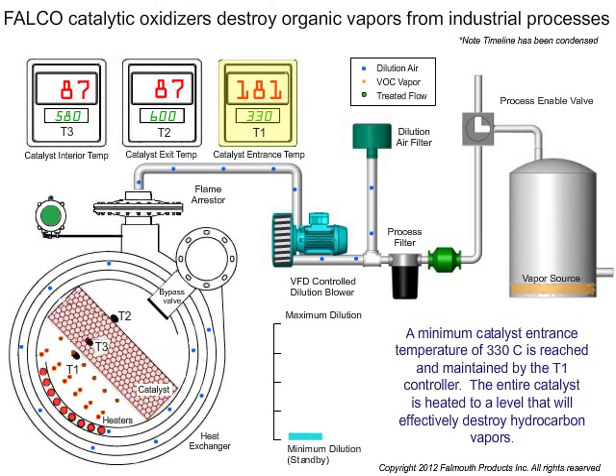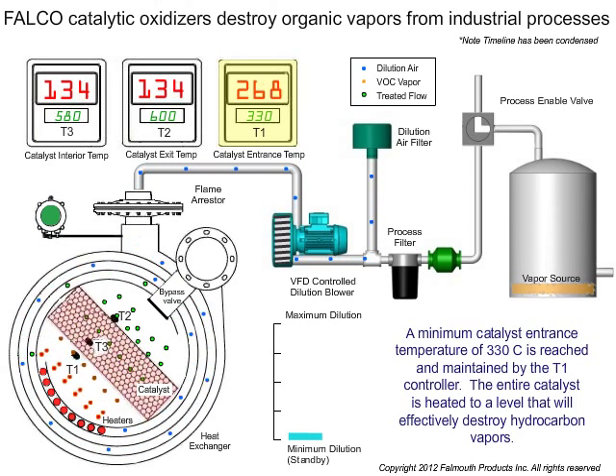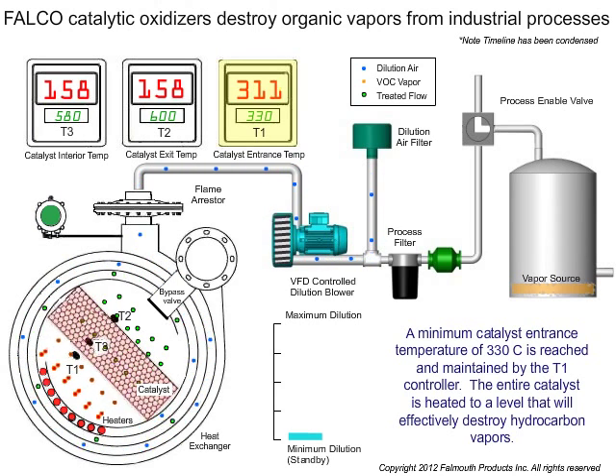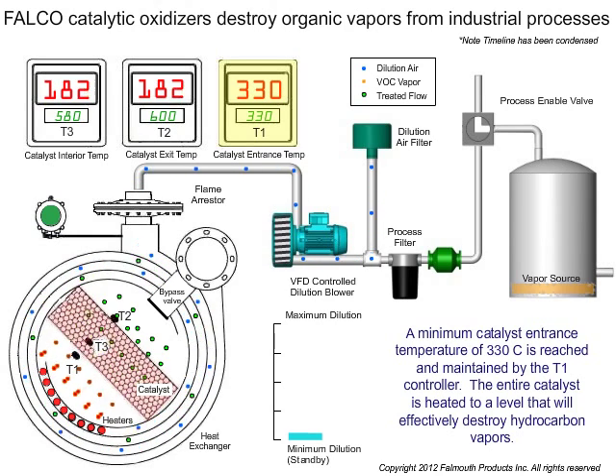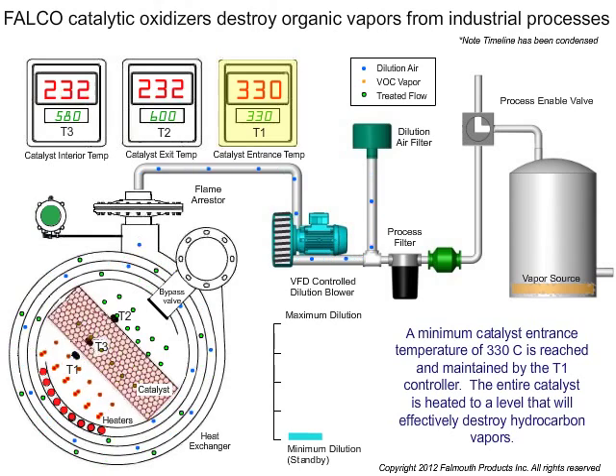The T1 controller regulates the heaters, which warm the catalyst bed with hot dilution air. A minimum catalyst entrance temperature of 330°C is reached and maintained by the T1 controller, heating the entire catalyst to a level that will effectively destroy hydrocarbon vapors.